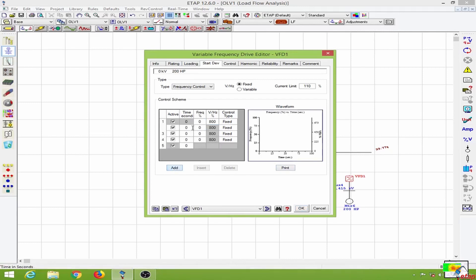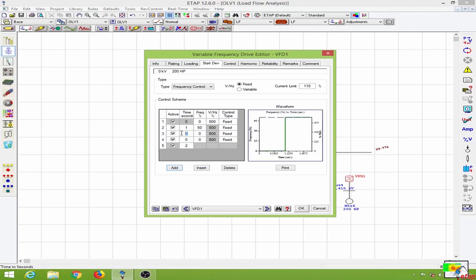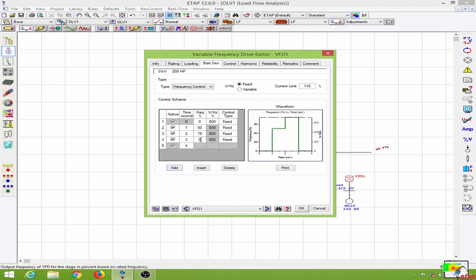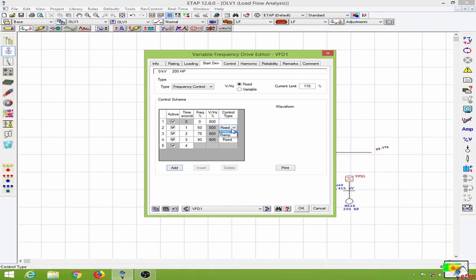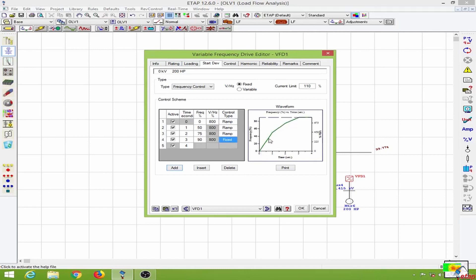At the first second I will have about 50 percent of my frequency, at the second second I will have 75 percent of my frequency, and at the third second I will have 90 percent of my frequency. I will change this to ramp because I want a smooth transition from 50 to 75 and so on. We have the smooth slope over here which varies the frequency with time, so I will click OK.